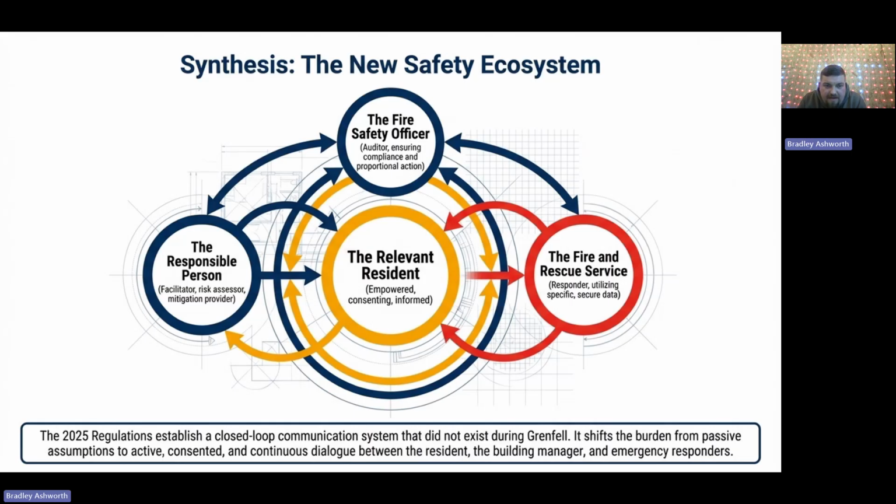So there could potentially be no staff, and that's likely to be the case in the majority of cases, present to evacuate those residents. So you may have to rely on the fire service in a worst case scenario to evacuate that resident. But it's about, well, what can I do in that scenario? Would it be safer, if you're on stay put or even on simultaneous evacuation, that the relevant resident, if their flat is on fire, tries to evacuate to the same floor that they're on, but just to the communal space, or even in the stairwell, where at least then the flat entrance door is a fire resisting door that'll self close, and then potentially they've gone past the lobby door as well. They could potentially have two fire resisting barriers between them and the fire while they're awaiting rescue. That's better than sitting in their flat that's potentially on fire.